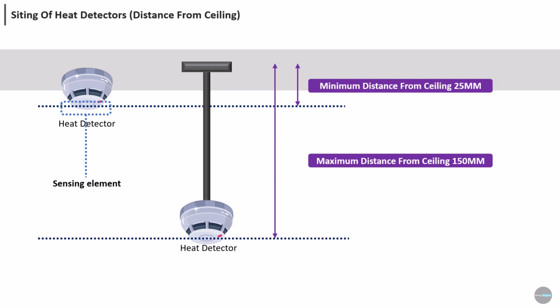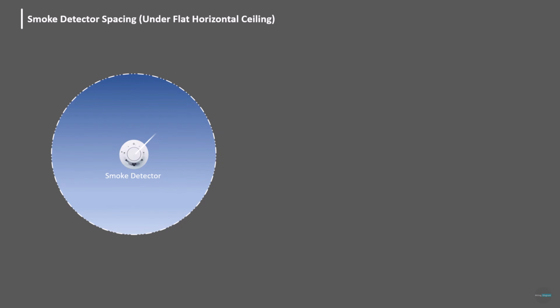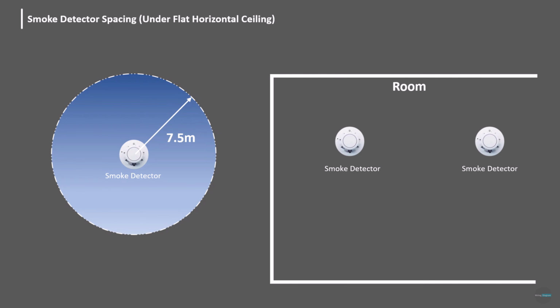This means the heat detector should be installed close to the ceiling so it can quickly sense any rise in temperature. Smoke detector spacing at flat horizontal ceiling. Under a flat ceiling, one smoke detector can cover an individual area of about a 7.5 meter radius. However, when we design a room or hall, the distance between two smoke detectors should be 10.6 meters, and the distance from the wall should be 5.3 meters.